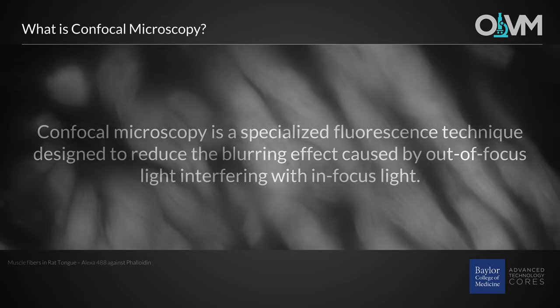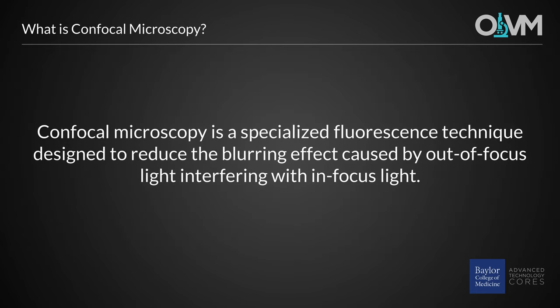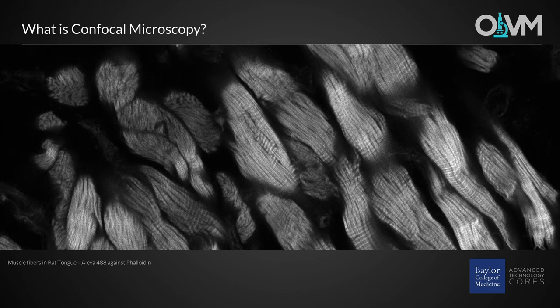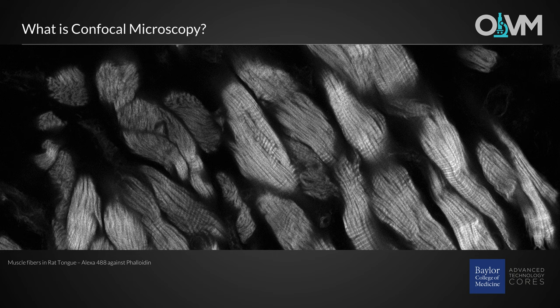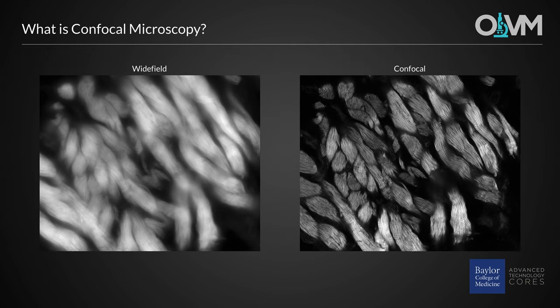In fact, the central purpose for which confocal microscopy is designed is to reduce the blurring effect caused by out-of-focus light interfering with in-focus light. This is the same field of the specimen we just observed with the traditional epifluorescence microscope. This time, the image was collected with a confocal. You'll immediately see the reduction of that out-of-focus blurring effect. Compared to a traditional fluorescence microscope, the confocal effect leads to increased contrast, sharpness, and resolution.